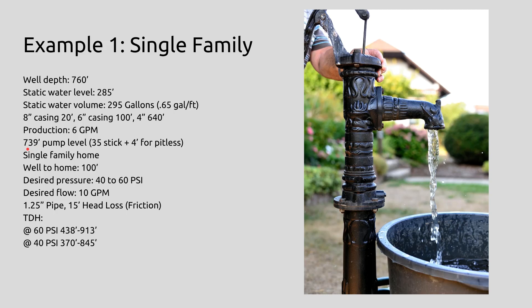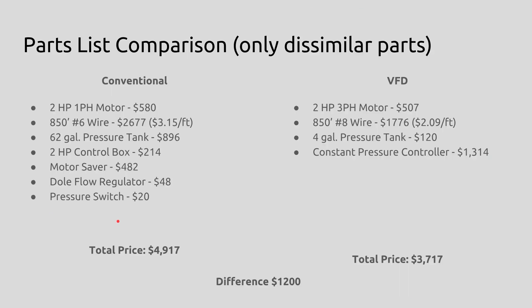We're going to put the pump at 739 feet, so it's going to be 35 twenty-one-foot sticks, and then we add four feet for the pitless depth to get us to that 739. It's a single family home. The distance from the well to the home is 100 feet. The desired operating pressure is 40 to 60 PSI, and the customer's desired flow is 10 gallons per minute. Now keep in mind this is completely made up, but I did get this information off of an actual well.